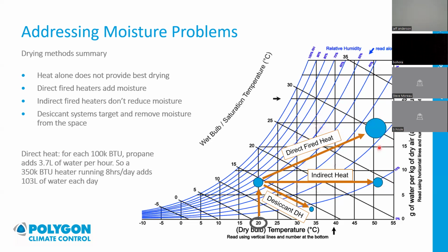So direct fired heat adds water, indirect fired heat doesn't affect water, and desiccant dehumidification directly targets moisture. We move to the right on the graph with desiccant technology because there's a heat gain on the wheel from refreshing it and pulling the water off. The wheel warms up and the air picks up some of that temperature, but that's not the purpose of the equipment—the purpose is to remove moisture. So we're essentially moving downward on the graph; this blue ball is shrinking, getting much smaller. Our absolute moisture, the vapor pressure on the right, is significantly less. By creating air with that really low vapor pressure, we force everything to dry.